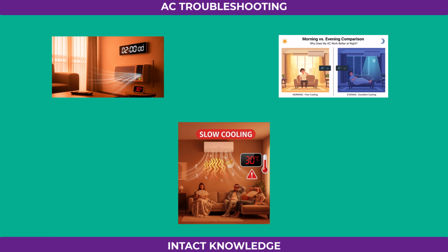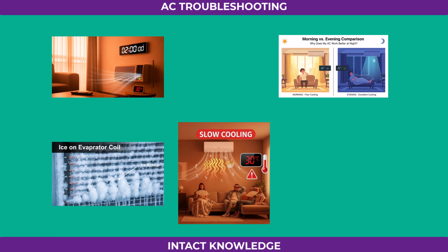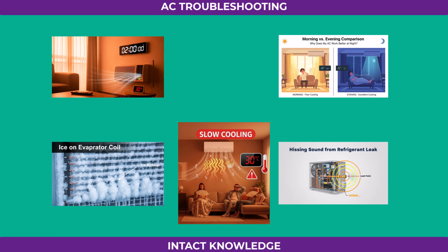You might also notice ice forming on the evaporator coil, which happens when the refrigerant is insufficient and the system can't absorb heat properly. Another sign is a hissing sound coming from either the indoor or outdoor unit. This noise can indicate a leak in the refrigerant line.